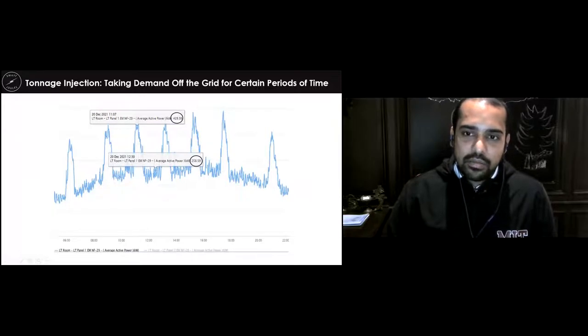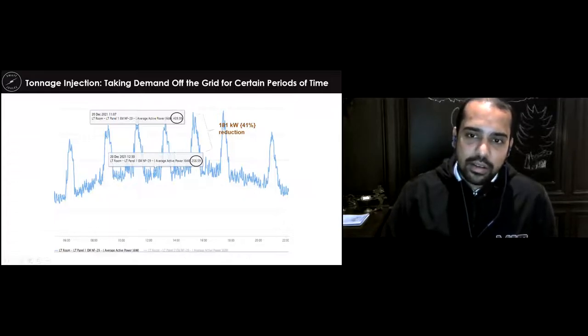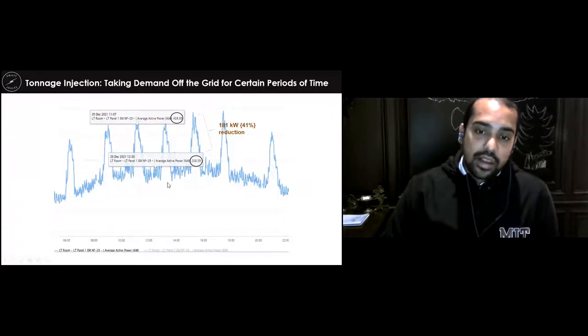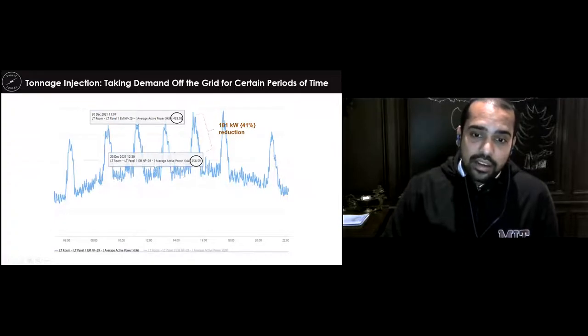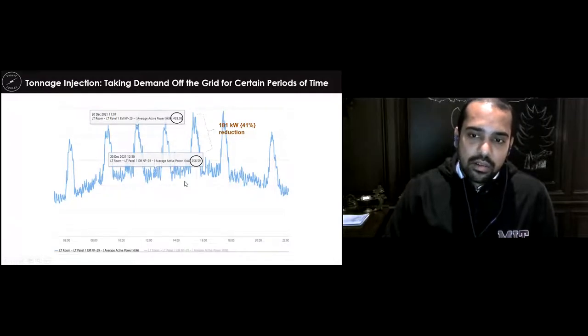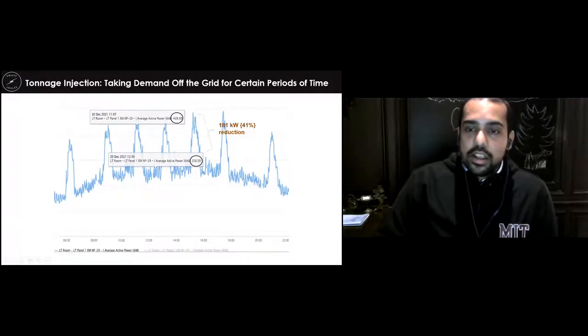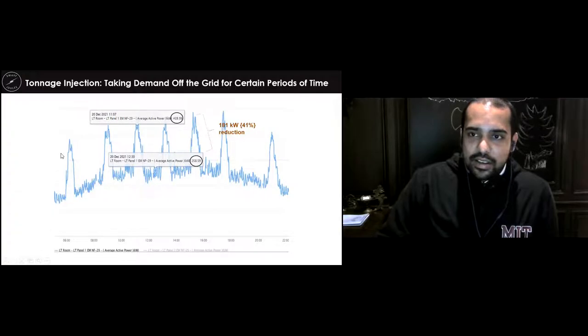Then you just turn everything off, and the power drops by 41%. And you observe, and you see, okay, now it needs to be turned back on, so it automatically turns back on. And then you have time intervals. You don't let it turn back on in less than 8 minutes because the compressor needs to be properly managed. So this is very interesting.